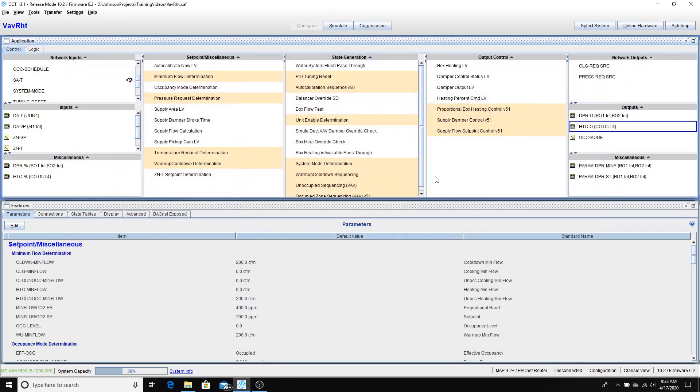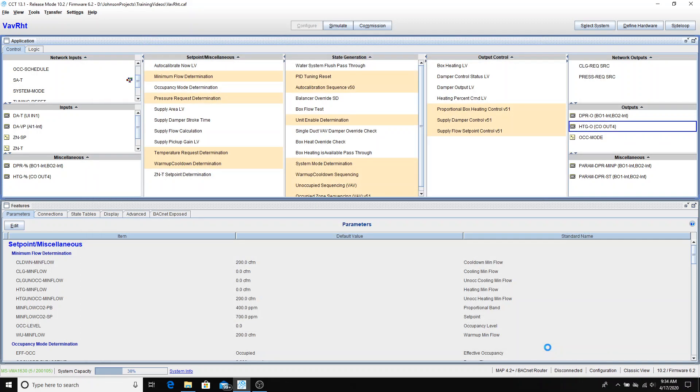Close. That concludes the configuration of this VAV box here. Now what we're going to do is do a save as, so we can keep all of the same settings, all of the changes that I made to the zone set point and the damper rotation and the heating output and save it as the next controller. So first I'm going to do a save and I'm going to save this one as VAV01 and I'm going to give it the suffix of 5 so that I know that that is its MAC address and I'll do a save on that.